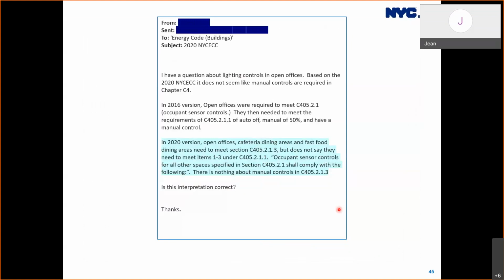Now let's jump to a lighting control question we received through the Energy Code email. So this question is about manual control in open plan office areas. It says in the 2020 version, open offices, cafeteria, dining areas, and fast food dining areas need to meet section C405.2.1.3, but it does not say they need to meet items 1 to 3 under C405.2.1.1, occupant sensor controls for all other spaces specified in section C405.2.1 shall comply with the following. There is nothing about manual controls in C405.2.1.3. So is this interpretation correct?